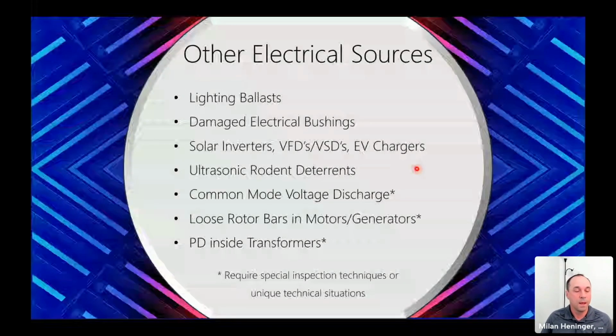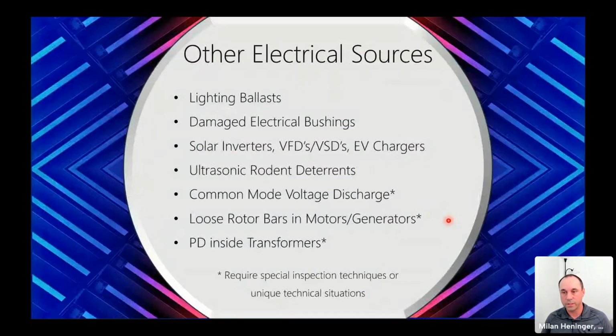If you can't, then figure out a way to shield them, because it will make doing any other ultrasonic inspections quite difficult. These last three require some special inspection techniques or a unique technical situation, but you can also detect common mode voltage discharge. You can find loose rotor bars inside motors and generators — we successfully did that in a hydroelectric generator at one point. And you can also detect partial discharge inside of transformer tanks. Again, these are a little beyond the scope of this, but these are some other opportunities and sources that you should be aware of.